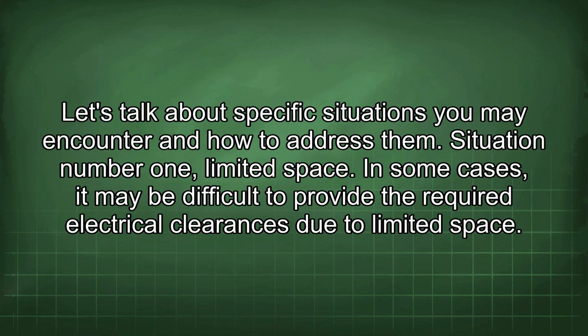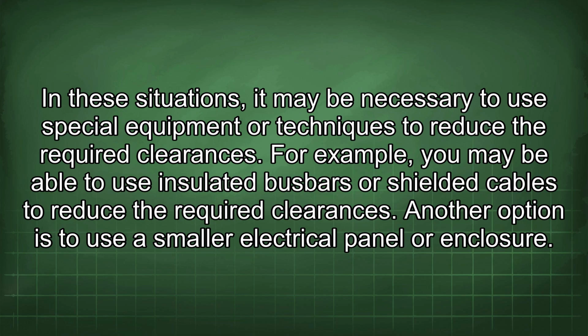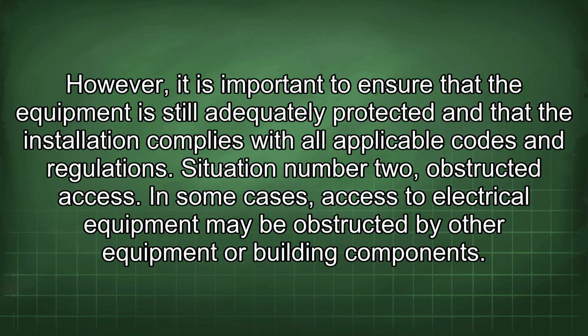Let's talk about specific situations you may encounter and how to address them. Situation number 1: limited space. In some cases, it may be difficult to provide the required electrical clearances due to limited space. In these situations, it may be necessary to use special equipment or techniques to reduce the required clearances. For example, you may be able to use insulated busbars or shielded cables to reduce the required clearances. Another option is to use a smaller electrical panel or enclosure. However, it is important to ensure that the equipment is still adequately protected and that the installation complies with all applicable codes and regulations.